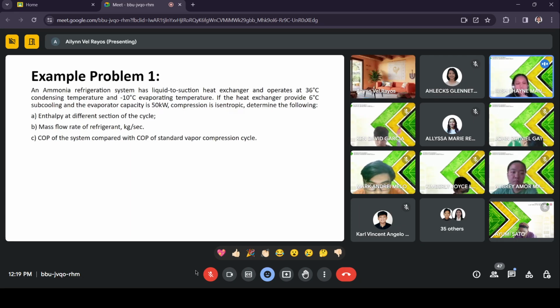Example problem 1: An ammonia refrigeration system has a liquid to suction heat exchanger and operates at 36 degrees Celsius condensing temperature and negative 10 degrees Celsius evaporating temperature. If the heat exchanger provides 6 degrees Celsius subcooling and the evaporator capacity is 50 kilowatts, compression is isentropic, determine the following: A. Enthalpy at different sections of the cycle. B. Mass flow rate of refrigerant in kilogram per second. C. COP of the system compared with the COP of a standard vapor compression cycle.